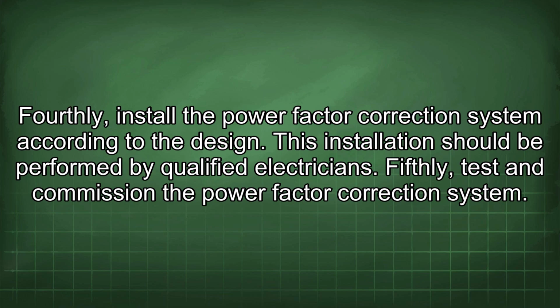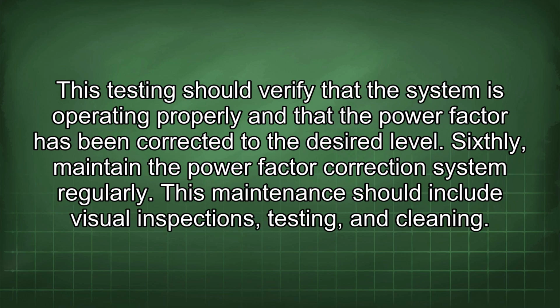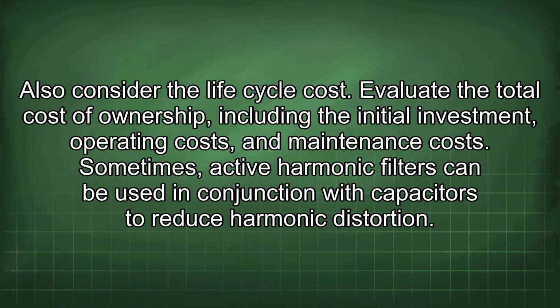Fourthly, install the power factor correction system according to the design. This installation should be performed by qualified electricians. Fifthly, test and commission the power factor correction system. This testing should verify that the system is operating properly and that the power factor has been corrected to the desired level. Sixthly, maintain the power factor correction system regularly. This maintenance should include visual inspections, testing, and cleaning. Also consider the life cycle cost. Evaluate the total cost of ownership, including the initial investment, operating costs, and maintenance costs.